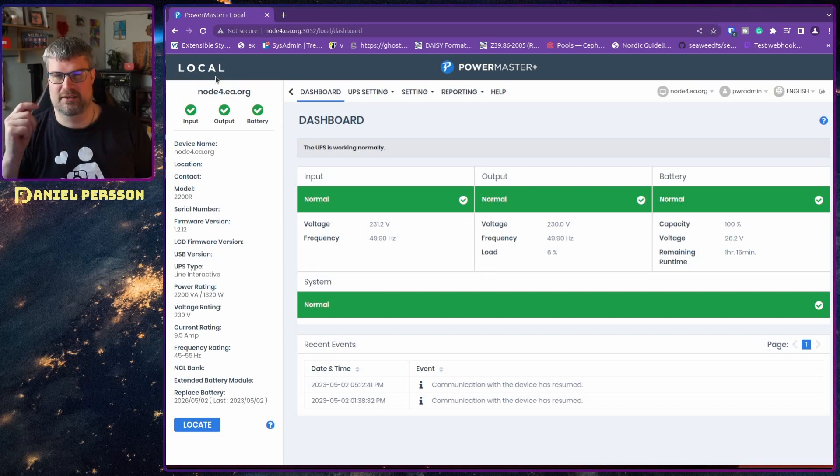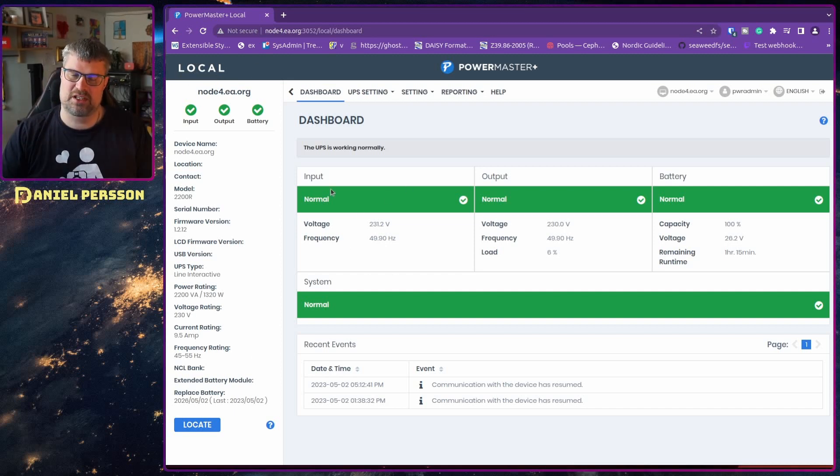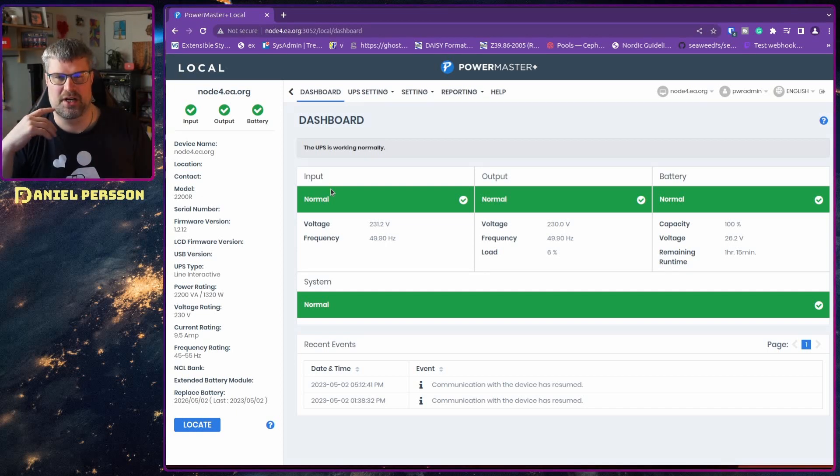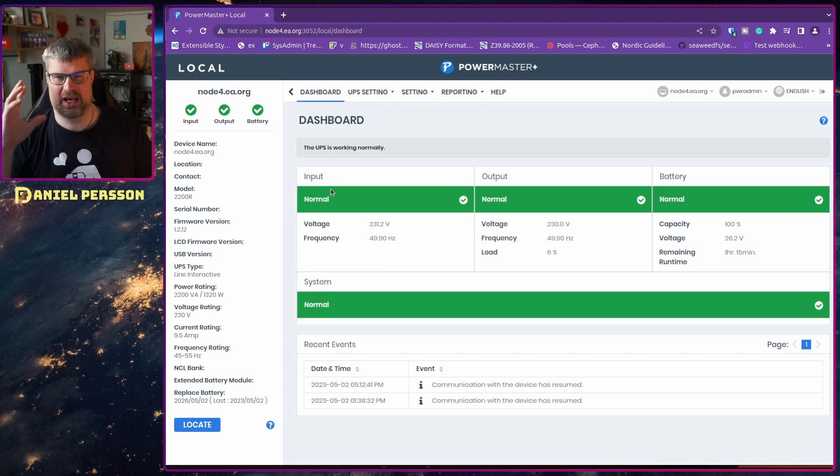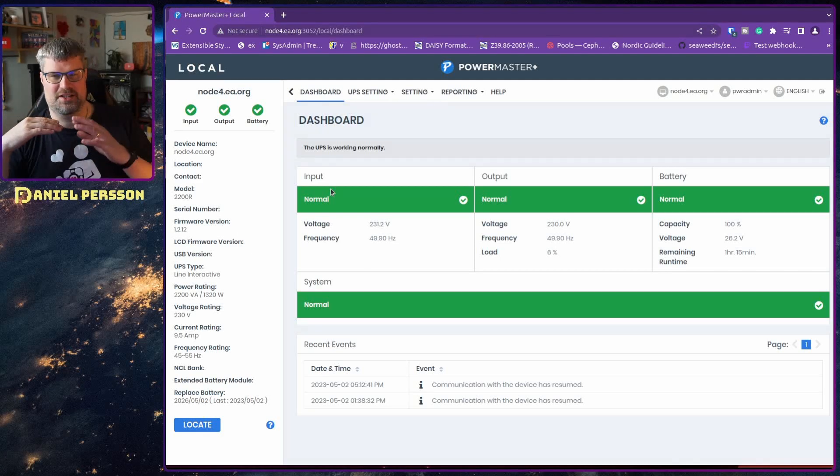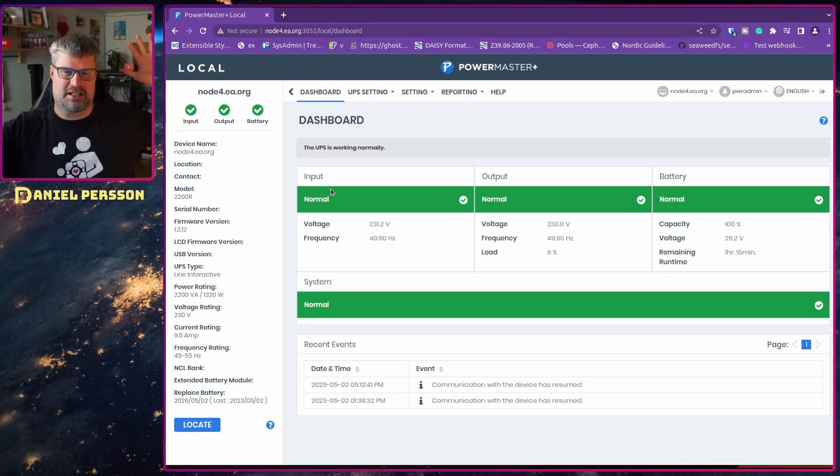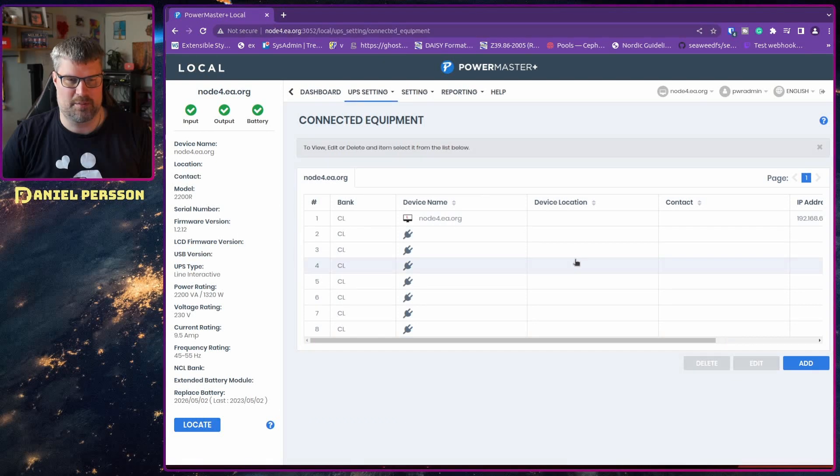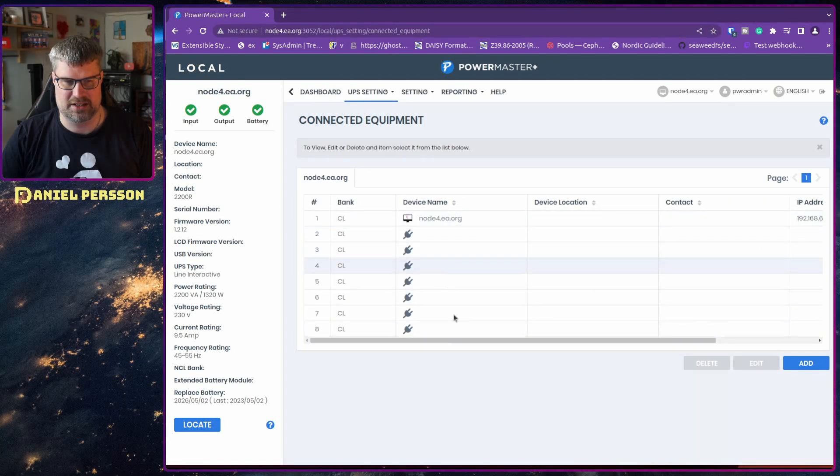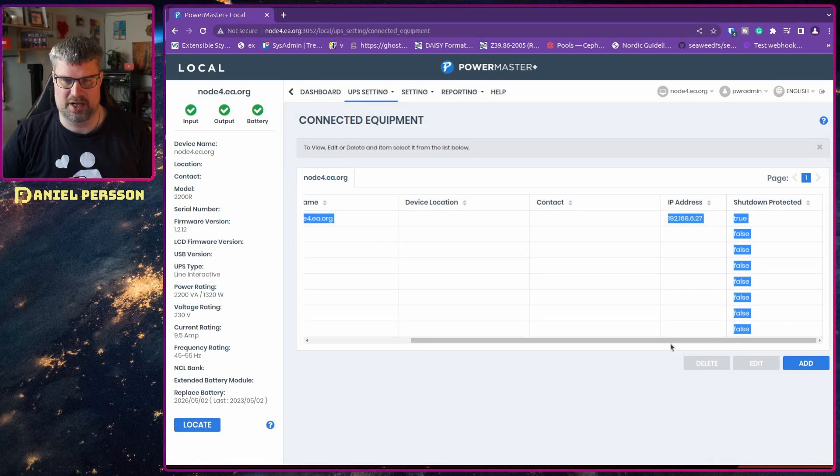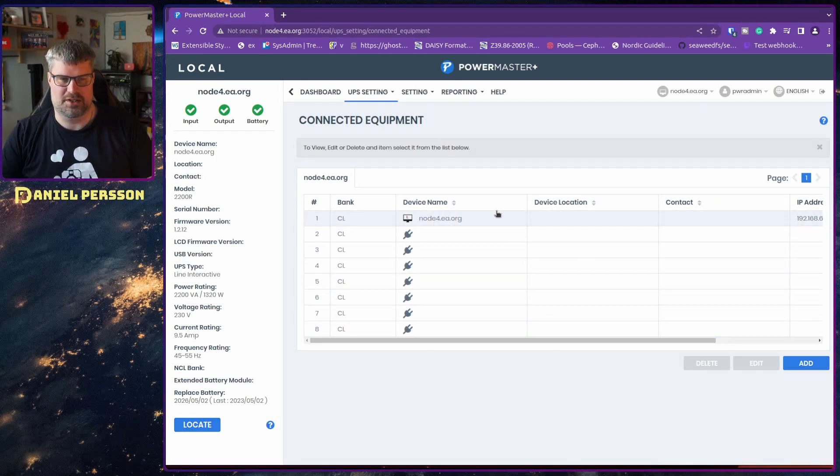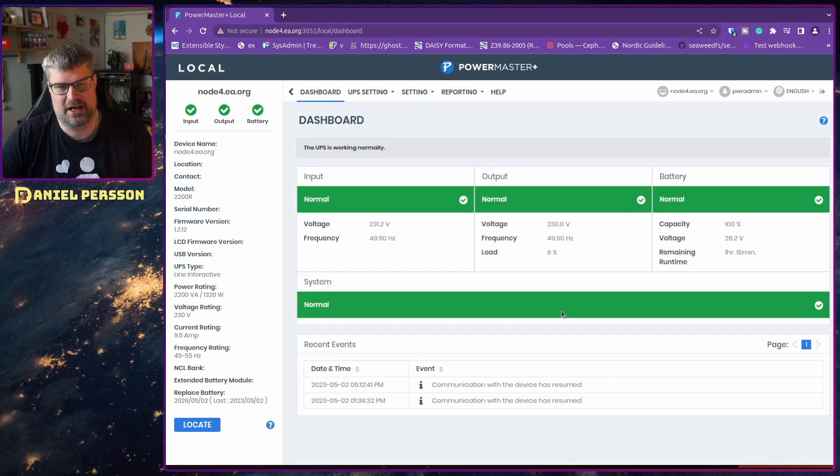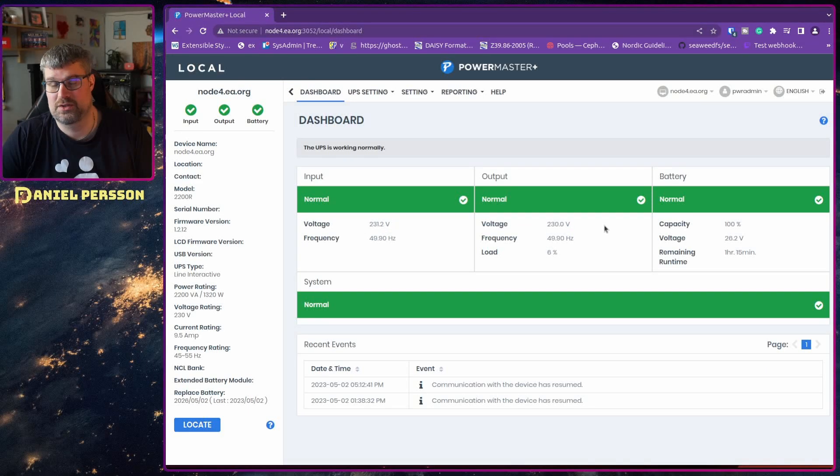The remote interface is something you install on all your other machines to tell the machines to shut down if you have an outage. In case the power goes out, you can tell the UPS to check power levels, and when you reach specific levels, talk to all the other machines and tell them to turn down. If you look at the connected equipment here, you can see I can have up to eight different things connected. I just have one machine at the moment, and currently shutdown protection is true.